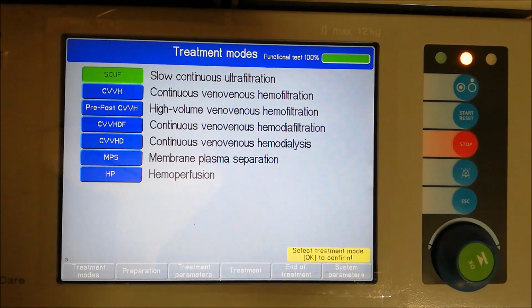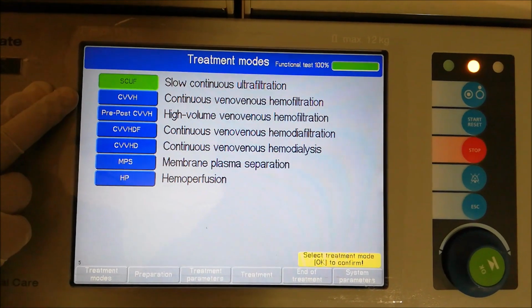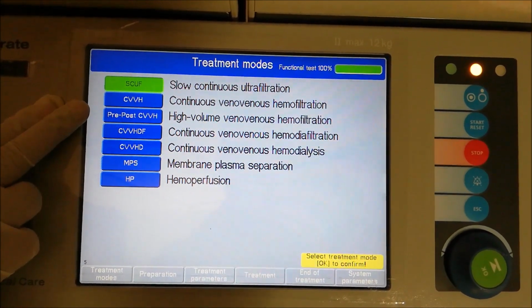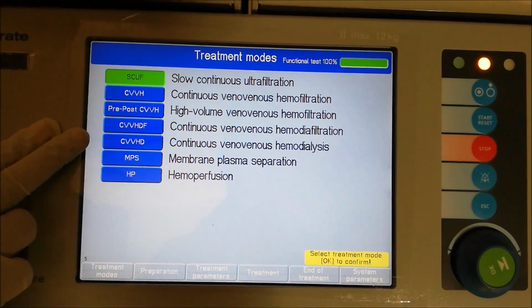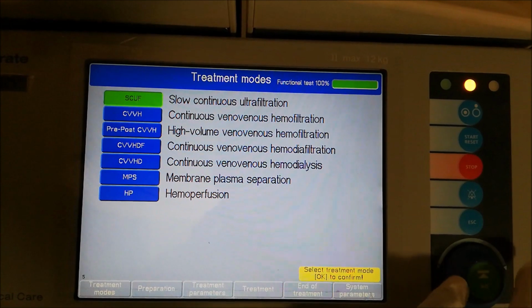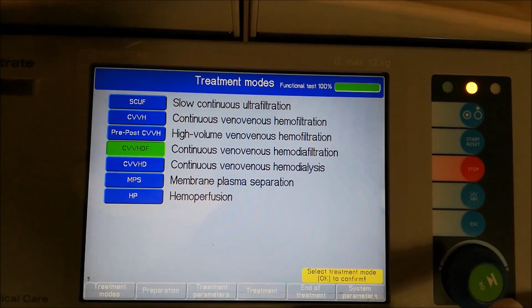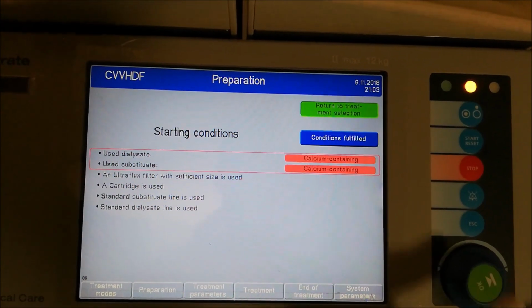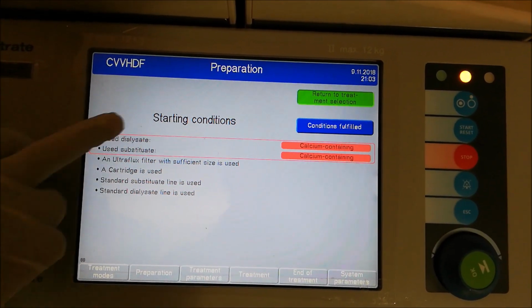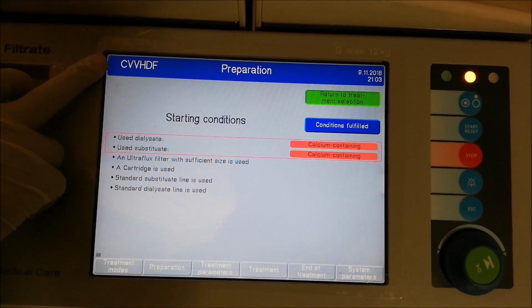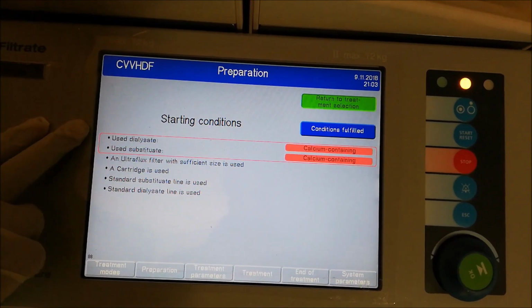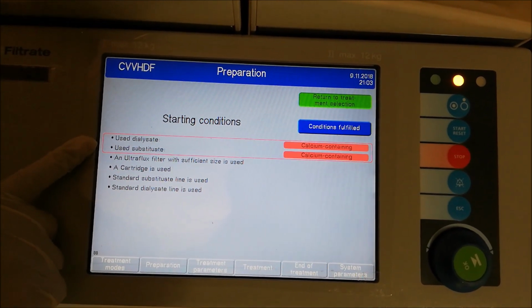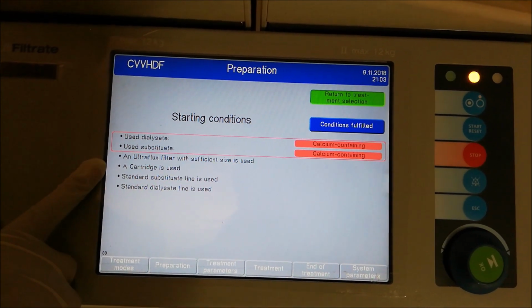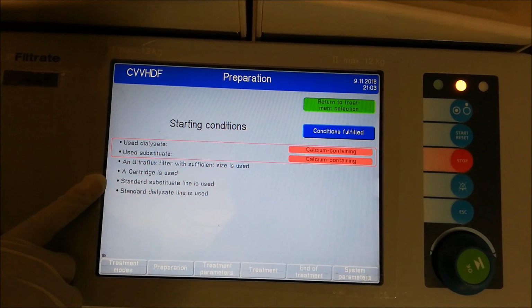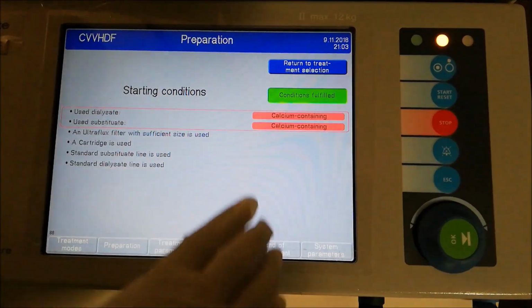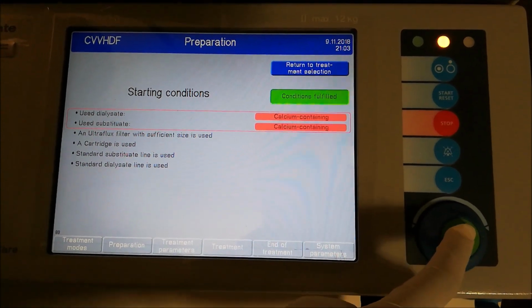Now treatment modes are on your screen, which are SCUF, CVVH, pre-post CVVH, CVVHDF, and CVVHD. In this demonstration purpose, we will select CVVHDF mode for priming purpose and press OK. Now you can see the preparation conditions for CVVHDF mode. And these conditions are: we are using dialysate, substitute, filter, a cartridge, and a standard substitute line and a standard dialysate line. Our conditions are fulfilled. Now we will press OK to move on.